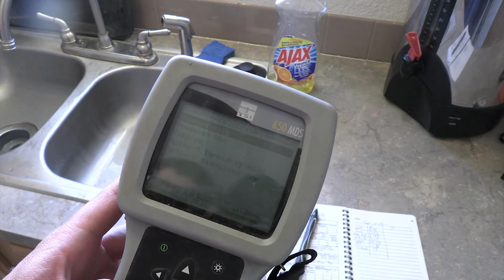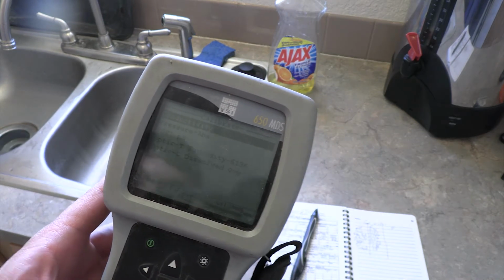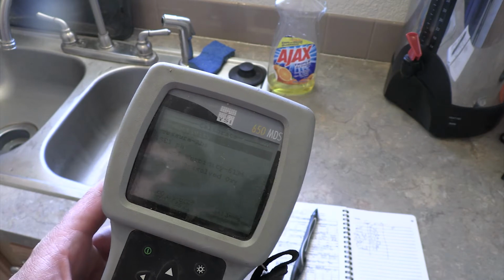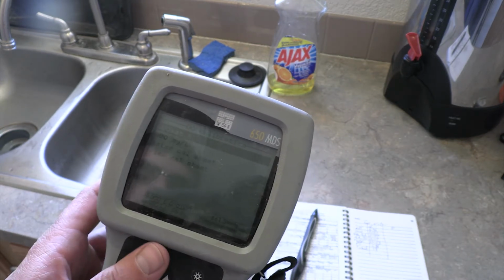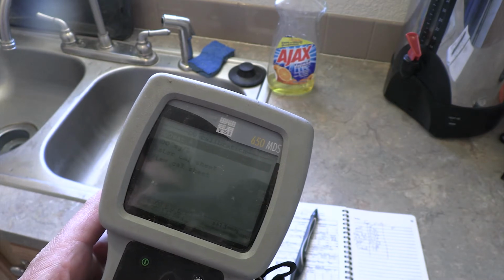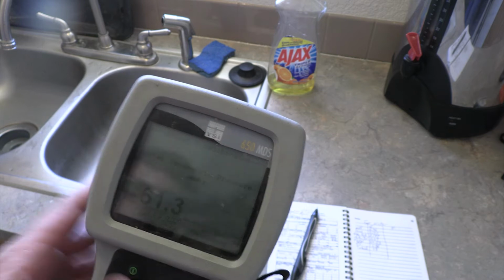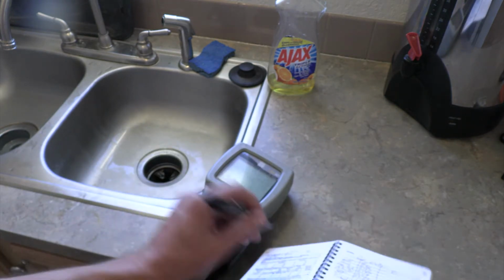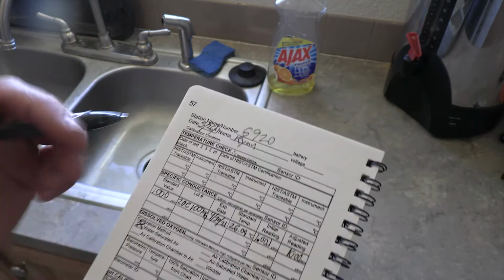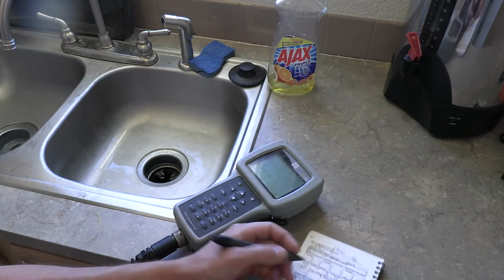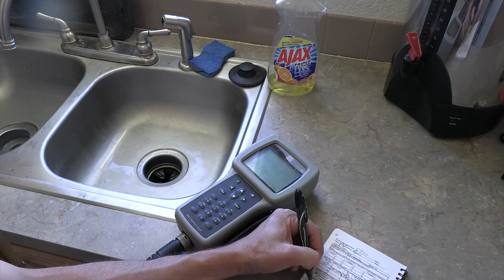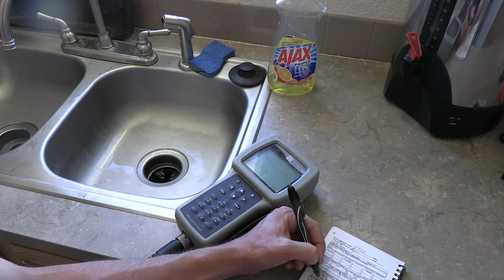Let's go ahead and go back to our last one. Escape out of the last calibration, and then let's go down to pressure or dissolved oxygen at the bottom. For this one we want to do DO saturated percent, and we just do 1 point. This is our barometric pressure, so let's write this down: 661.3. Okay, 661.3. And then press enter.